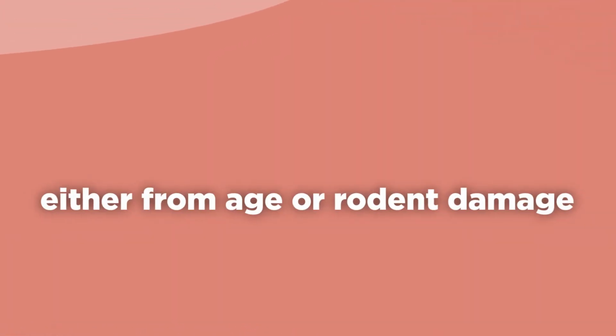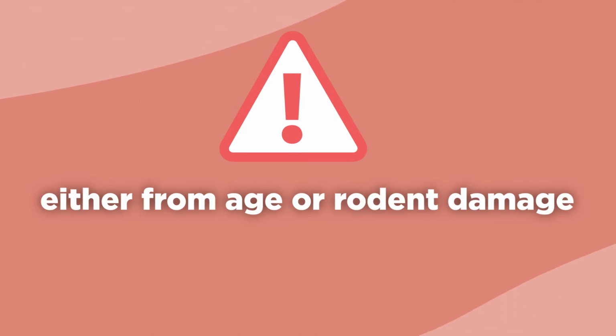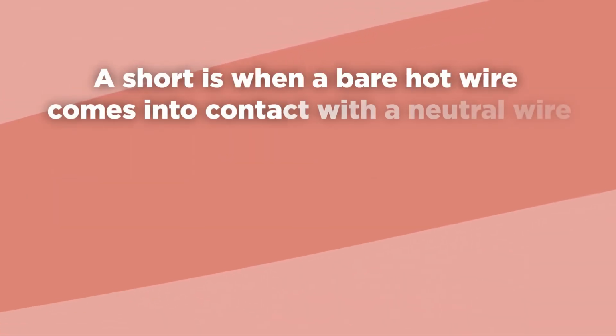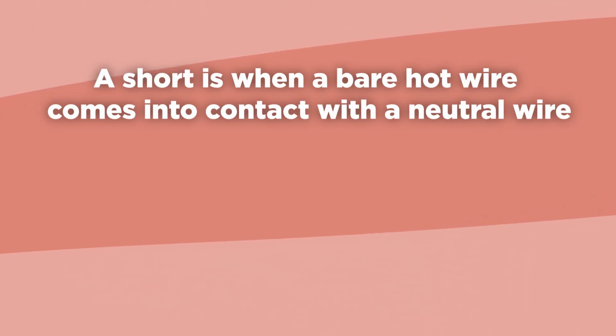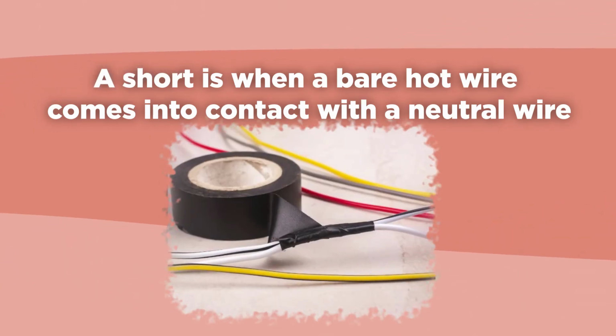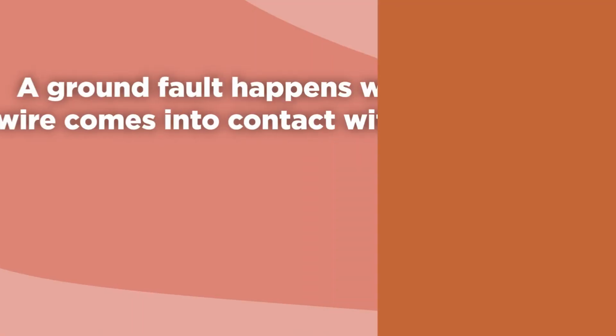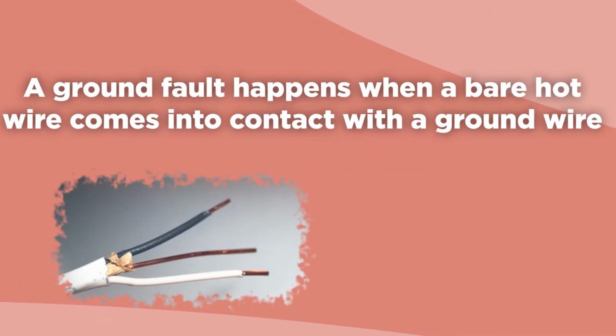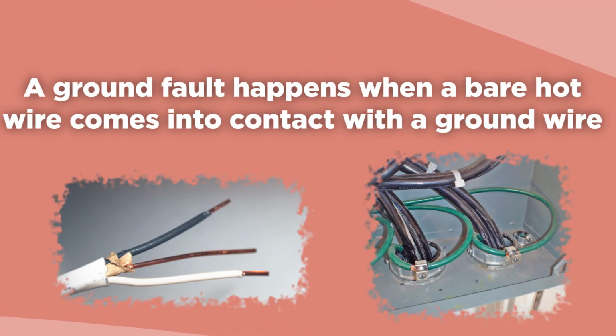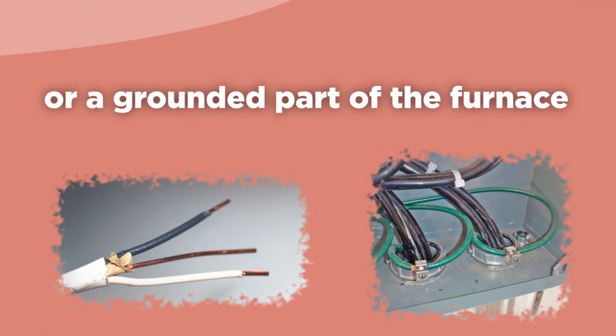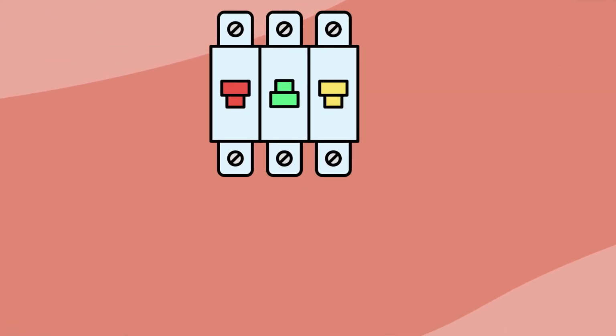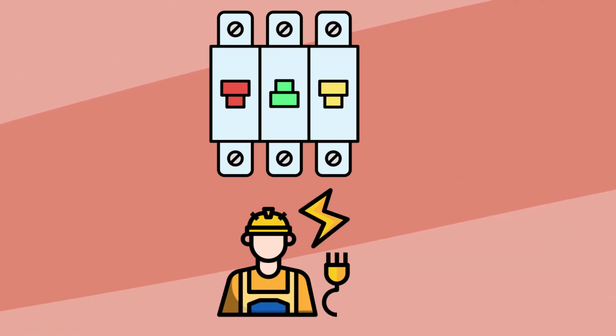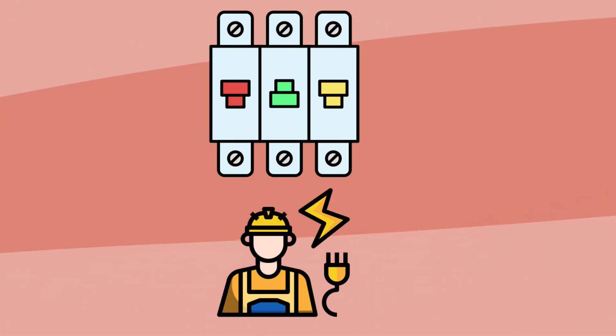3. Wiring problems, either from age or rodent damage, can create a short in a wire and ultimately trip the breaker. A short is when a bare hot wire comes into contact with a neutral wire. This can often be handled by insulating the wire with electrical tape. A ground fault happens when a bare hot wire comes into contact with a ground wire or a grounded part of the furnace. The breaker will immediately trip if a hot wire touches the metal box. Any wiring issues should be taken care of by a trained HVAC technician.